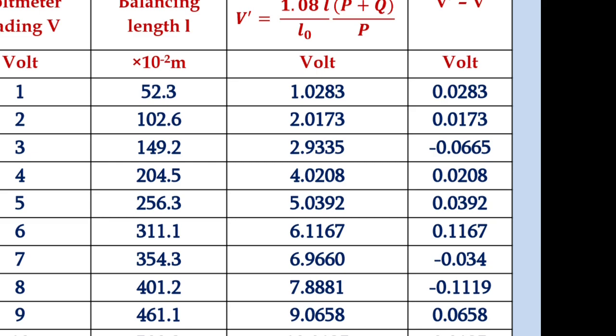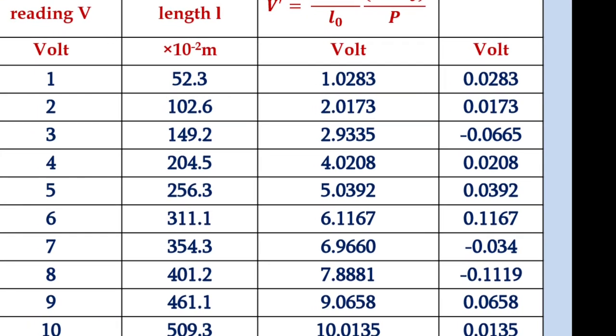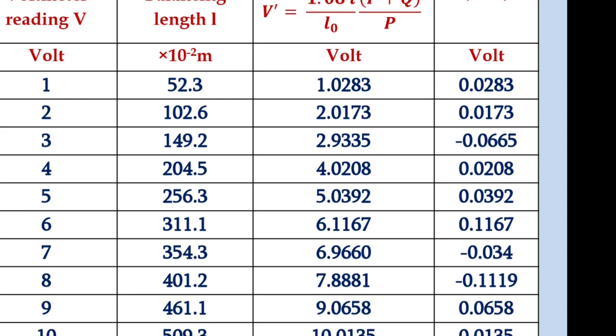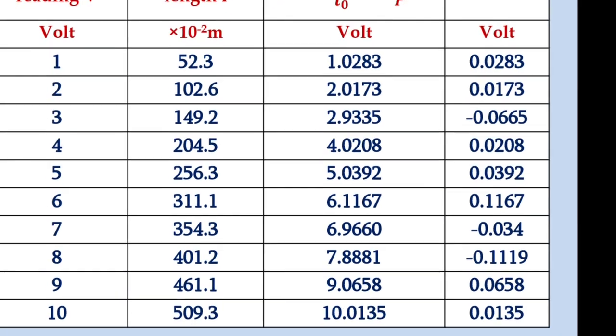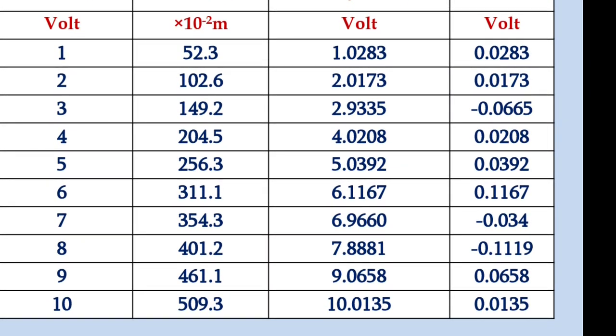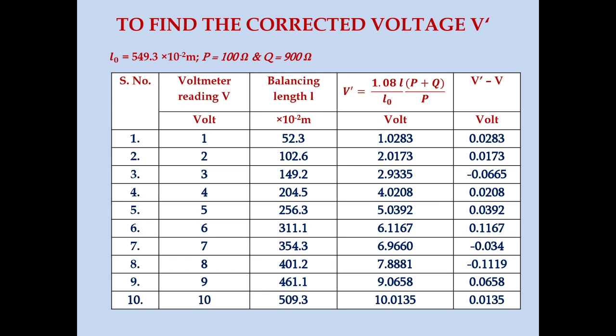So here we have got the correction both in positive as well as in negative values. And when you do a correction, it should be around or less than 0.5 volts, or you can say not more than 0.2 volts. So when you do a calibration graph, both for the low range voltmeter as well as the high range voltmeter, the correction obtained should be less than 0.2 volts. If you get more than that, then the correction is more and we have not calibrated it, or it is not good to use that voltmeter for the experiments.